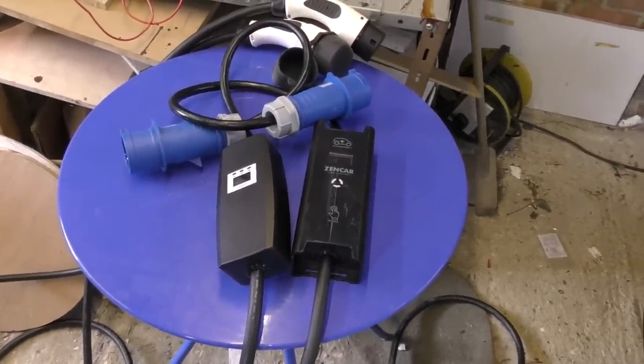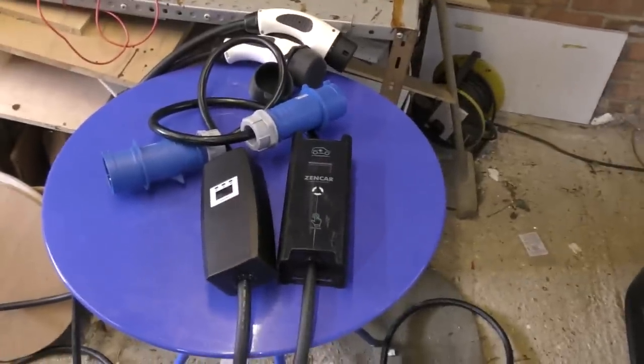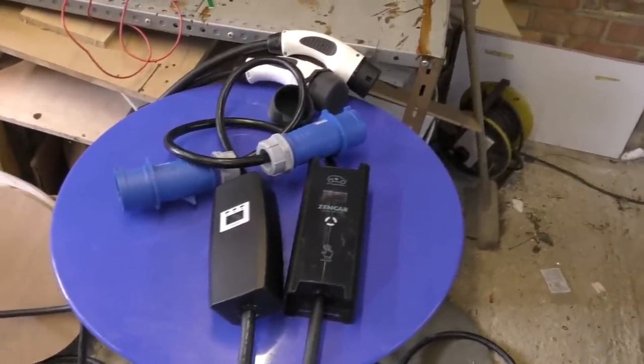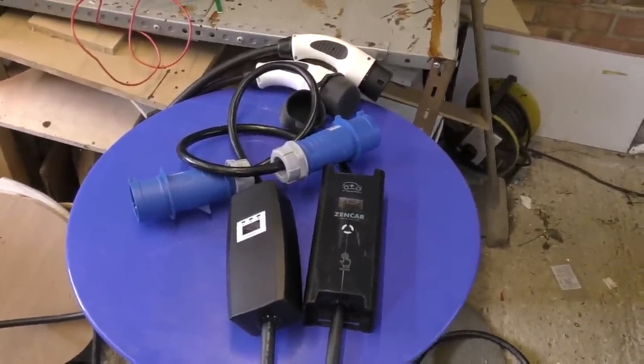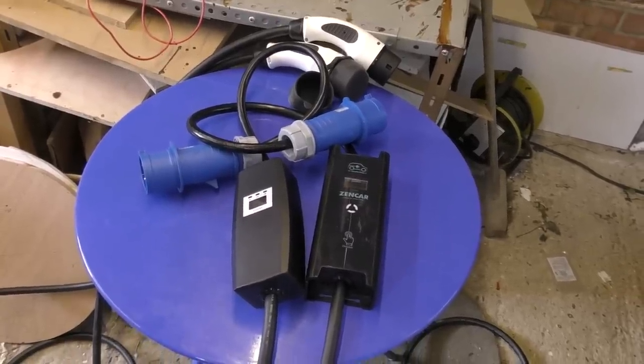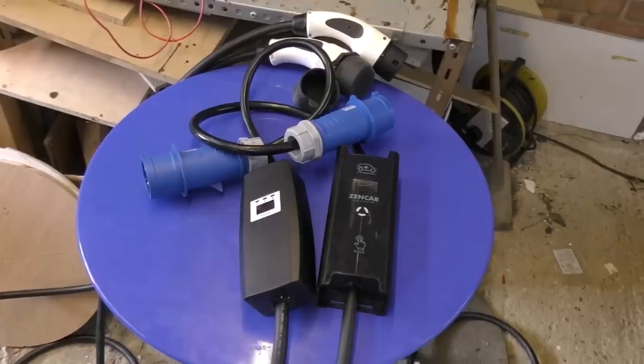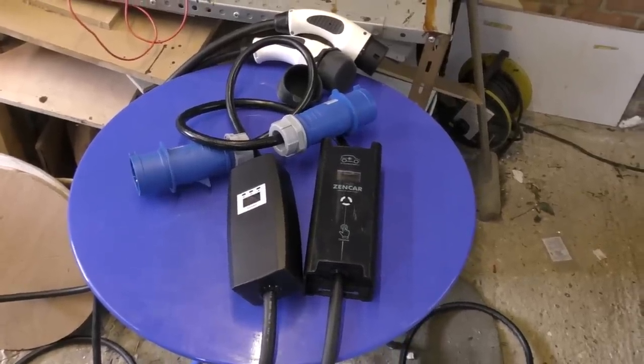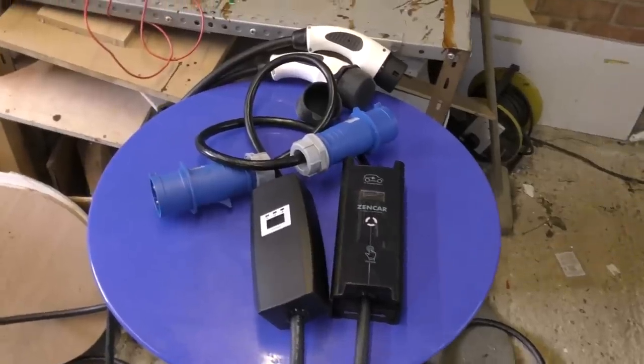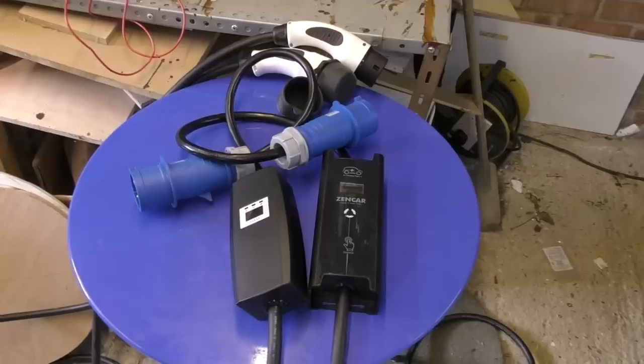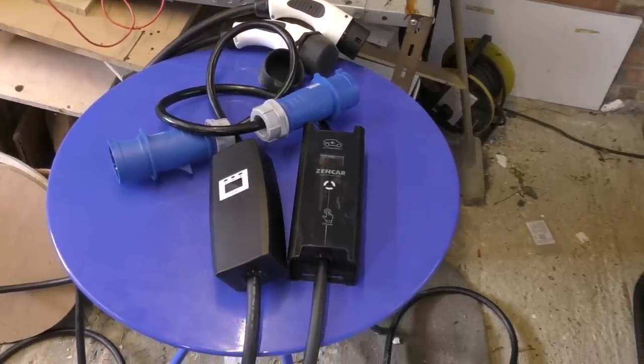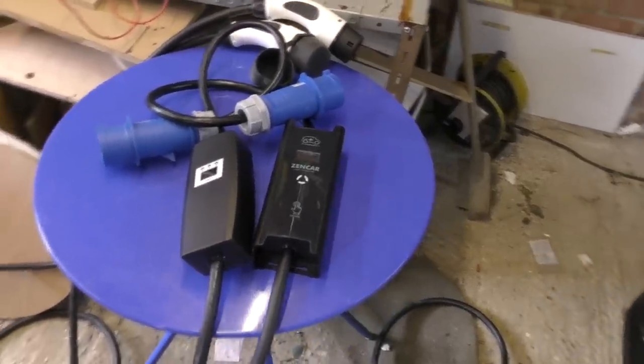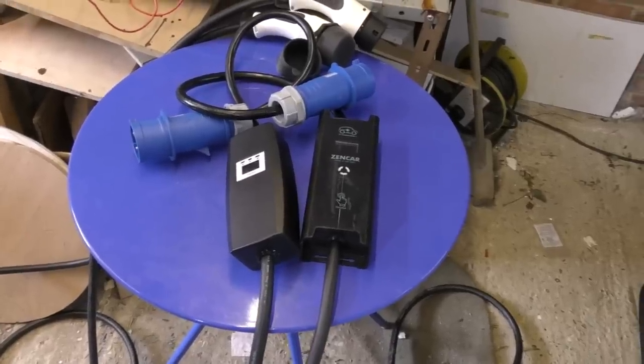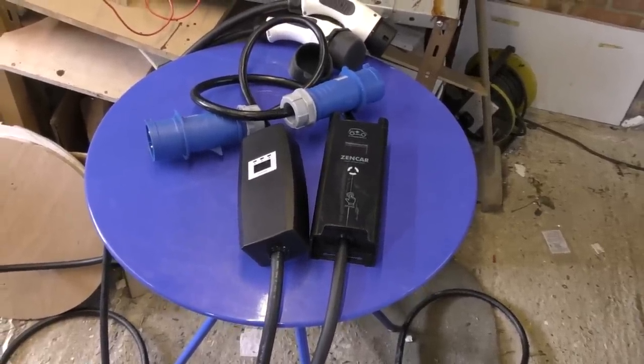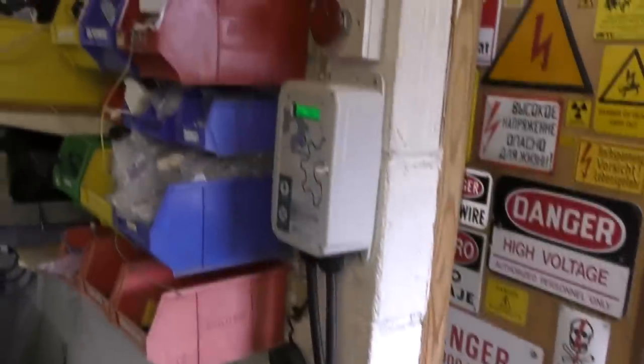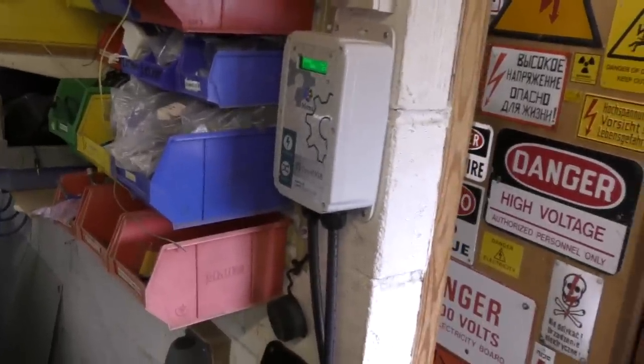But secondly, these things would typically be plugged into a circuit that has some residual current protection upstream. And if there's any DC leakage, this can cause a problem, because that DC leakage can saturate the current transformer in the upstream protection device and actually prevent it tripping on genuine AC current faults. So if this is sharing a circuit with other load or even just wiring, a DC leakage fault can actually stop that tripping. The UK wiring regulations only apply to fixed wiring, so if you're installing a fixed wall mount charger like this, then the charger should have DC protection.